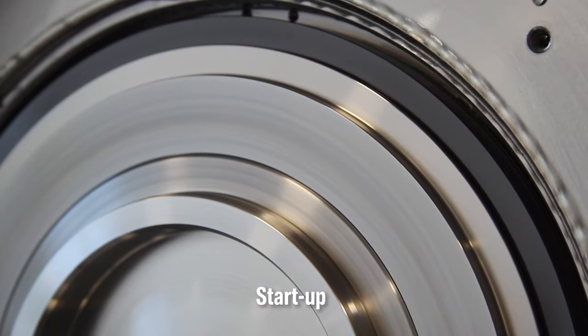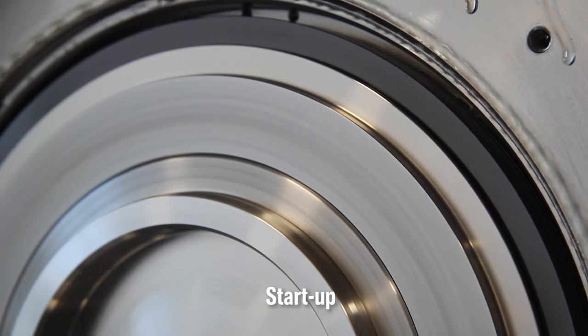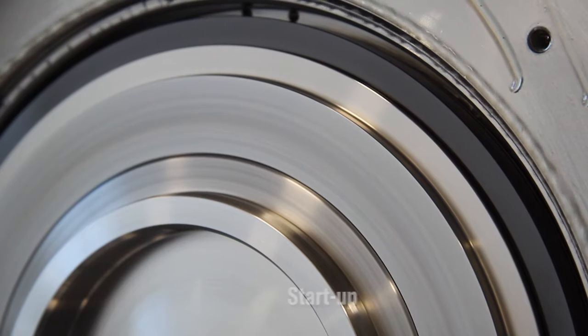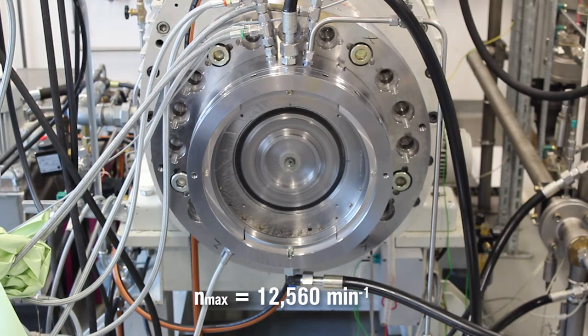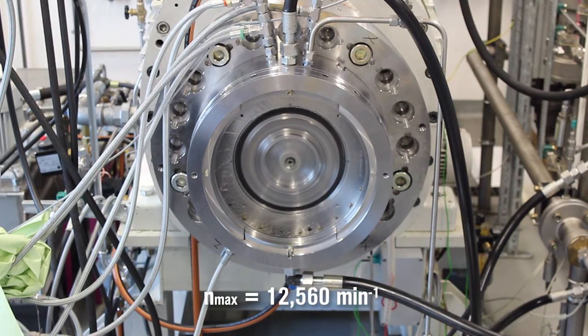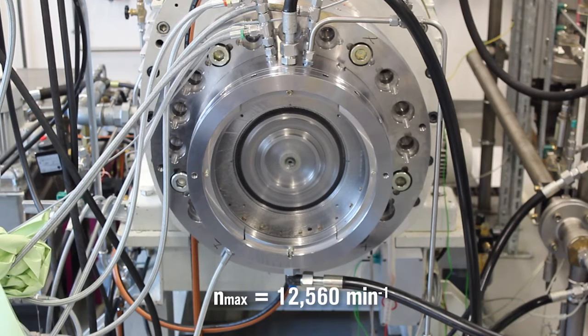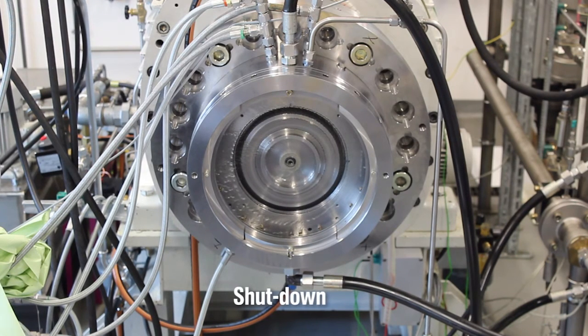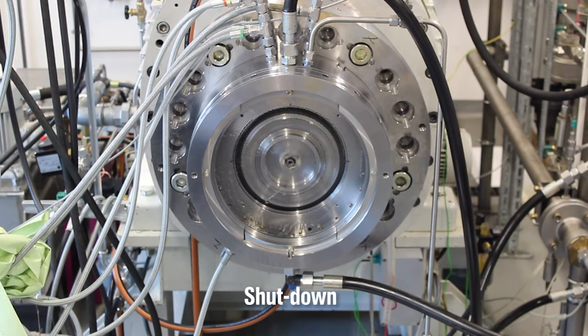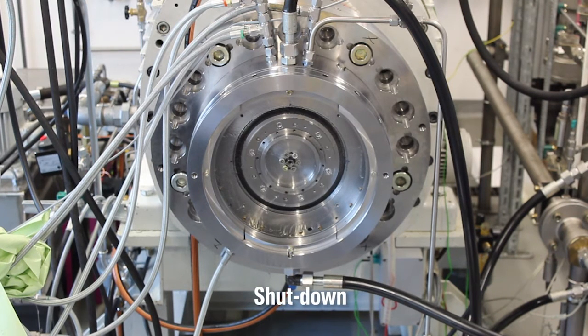Shortly after startup, it can be clearly seen how oil present at the seal is returned to the bearing housing via the outer diameter of the seal. The speed is increased to 12,560 revolutions per minute. After a few minutes, the test rig is shut down until stationary. This marks the end of the test sequence.